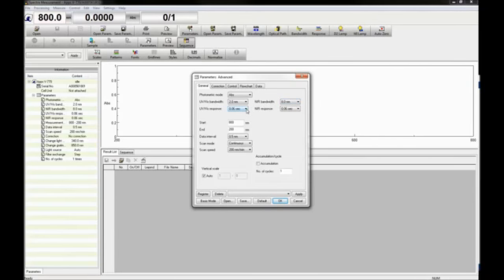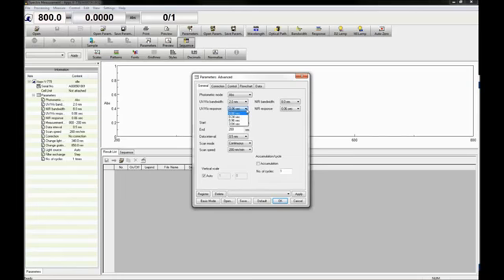The response time is the time spent accumulating photometric or absorbance values. The response time can be increased to get better signal to noise for samples with small absorbances.